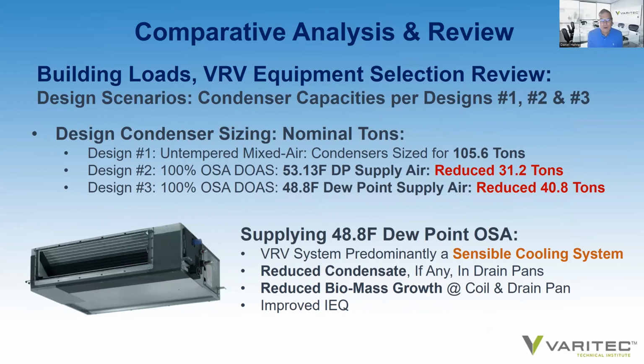So what does that mean? Well, design number 2 offers a VRV tonnage reduction of 31.2 tons, and a 48.8 degree dew point supply air can reduce the tonnage of the VRV system by 40.8 tons. Consequently, I remember having this discussion with Judy Peters when she did the energy analysis, and one of the comments she made when she did the evaluation for the low dew point DOAS solution was that the VRV system became predominantly a sensible cooling system, reducing significantly the amount of condensate that would form at the fan coil cooling coil unit. And this would also help us to avoid condensate pans filling with water and reduce the risk of biomass growth and its impact on building IEQ.